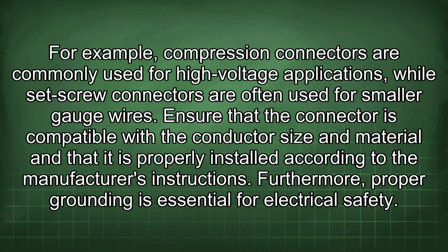For example, compression connectors are commonly used for high-voltage applications, while set screw connectors are often used for smaller gauge wires. Ensure that the connector is compatible with the conductor size and material and that it is properly installed according to the manufacturer's instructions. Furthermore, proper grounding is essential for electrical safety.